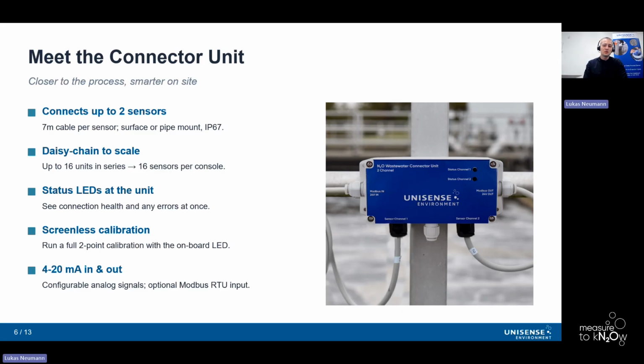This is a small IP67 box that you can mount close to the tank. This connects up to 2 sensors via their respective 7-meter cables. You can mount it on a railing or a pipe, and then you can daisy chain these or mount them in series up to 16 units in a row, giving a full 16 sensors per console.